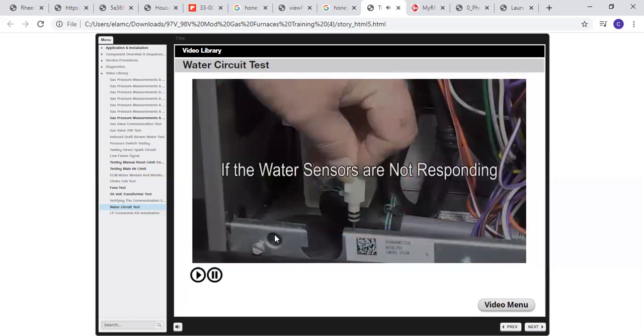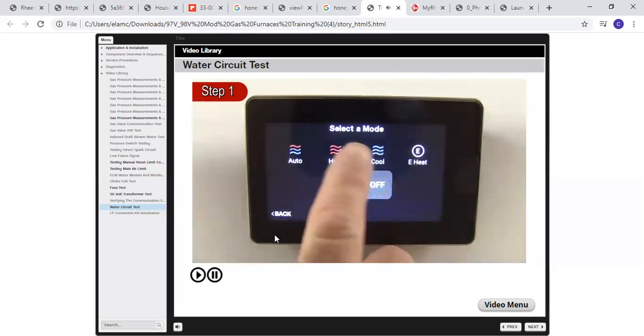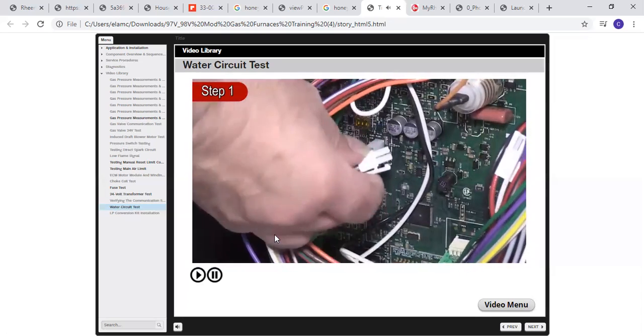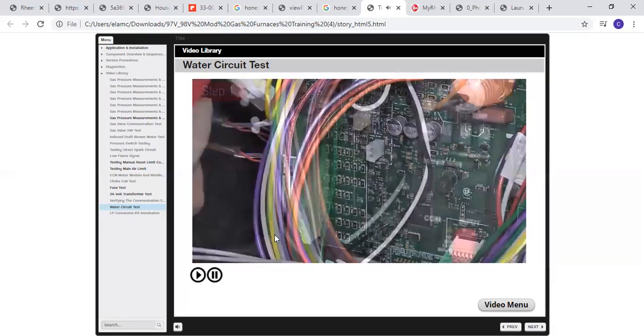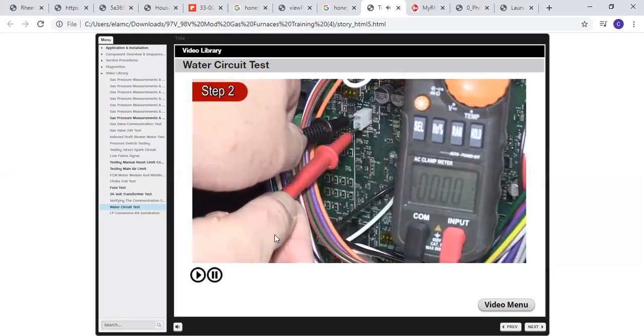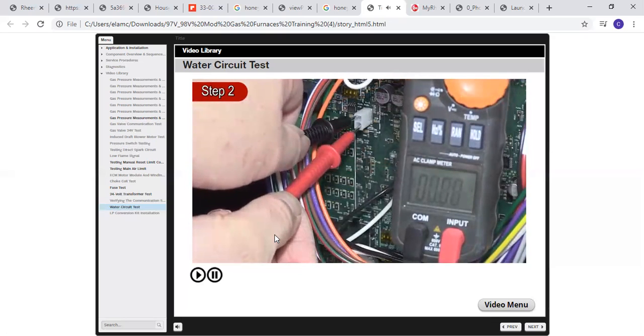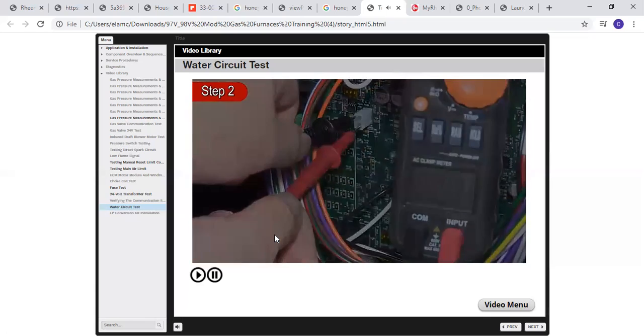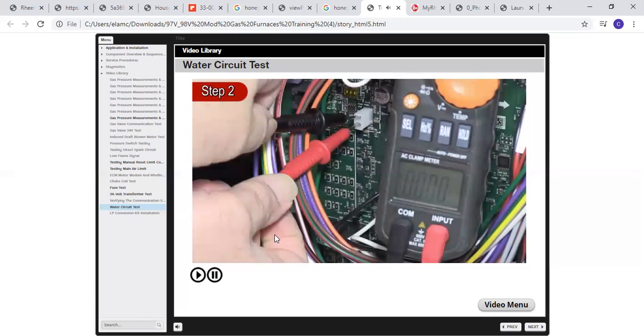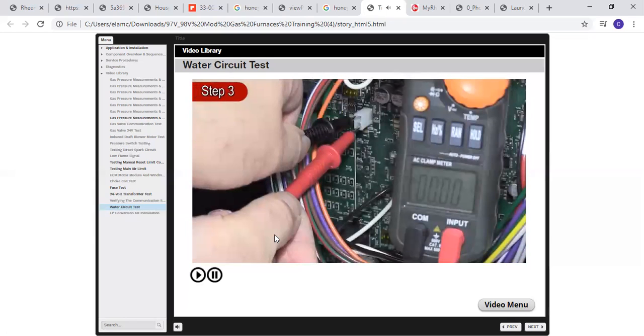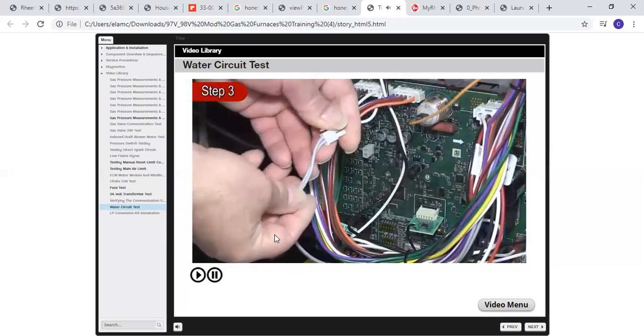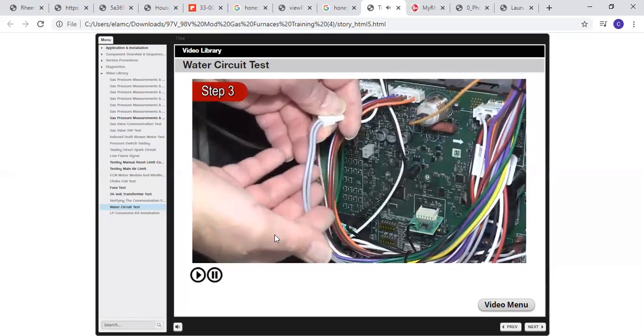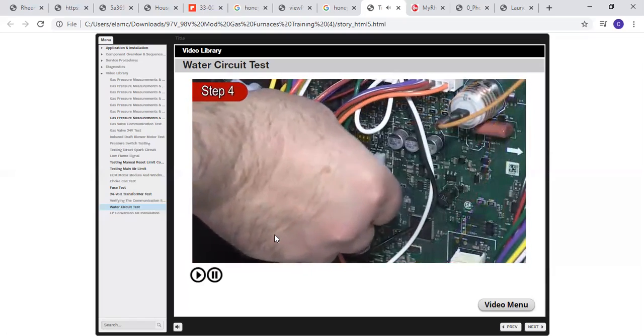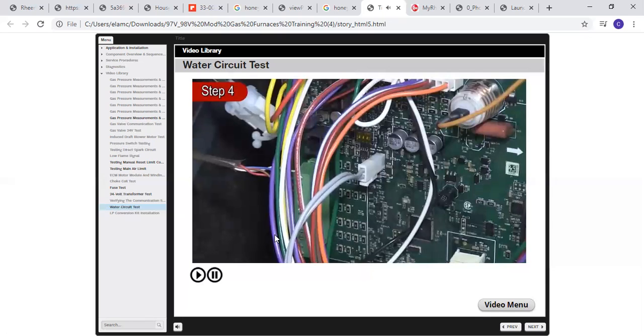If the water sensors are not responding: Step 1. Call for heat and unplug the water sensor plug PL-4 at the integrated furnace control. Step 2. Check for a fluctuating 0 to 2 volts DC voltage between the two water sensor pins and integrated furnace control plug PL-4. If the voltage is not present, replace the furnace control board. Step 3. If voltage is present, check for and repair loose wiring connections between plug PL-4 and the water sensor. Step 4. Reattach the water sensor plug when testing is completed.